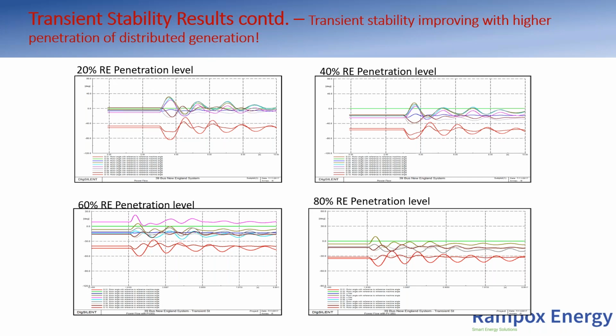That means they are not loaded as much as they would be. A synchronous machine loaded at full load compared to when it's loaded at half or even lower will generally exhibit better stability. So that's what is happening here: your synchronous machines are pulling back because of the feed coming from your loads, and as a result you have improved stability. Sometimes we need to talk about these things because they are there. It's one positive influence. It might not be looking at things in their full entirety, because there are other elements where you may find that you have problems with synchronizing torque, but I'll get to that. That's what will normally happen with distributed generation.